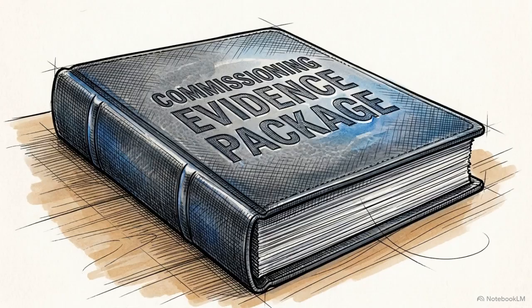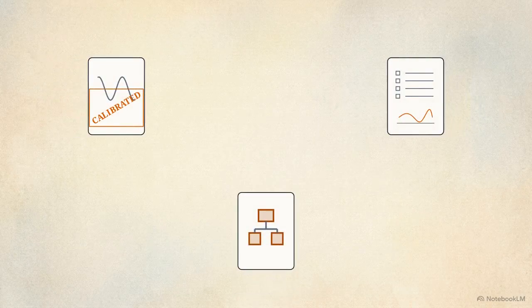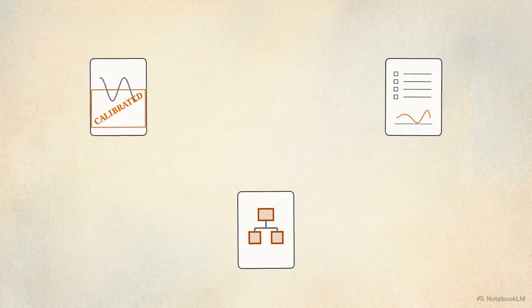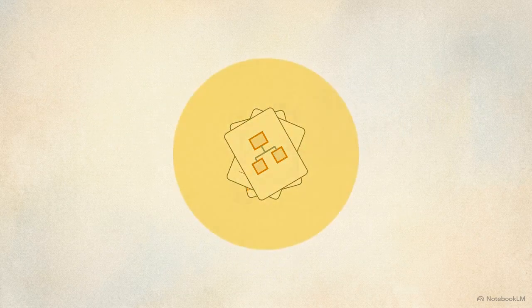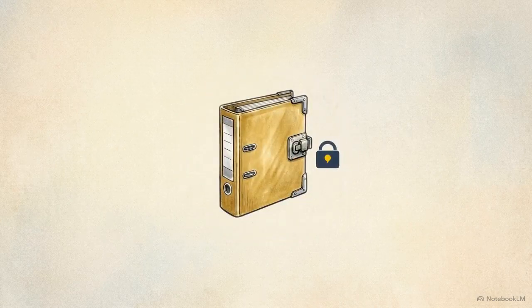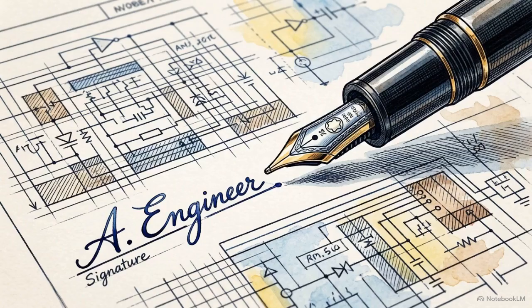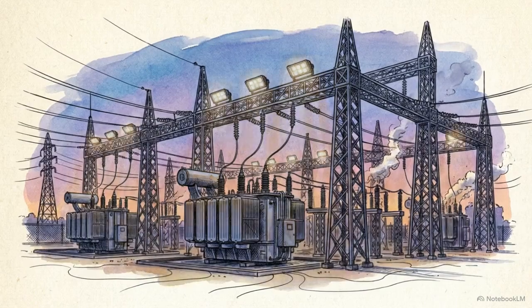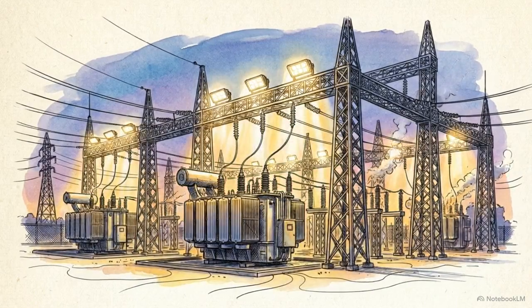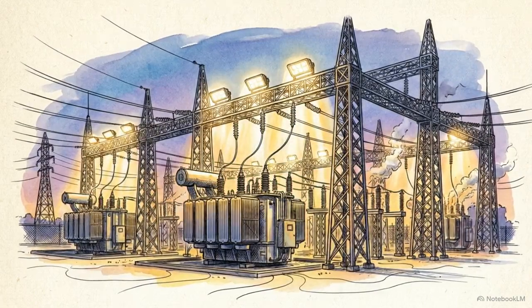The lead engineer then compiles the evidence package. Every calibration certificate, signed test sheet, and specific standards reference is bound into a single traceable document, proving compliance. This final evidence package transforms thousands of technical readings into a documented record of operational readiness. By signing off on these results, the commissioning team establishes the final layer of professional accountability required to energize the board.